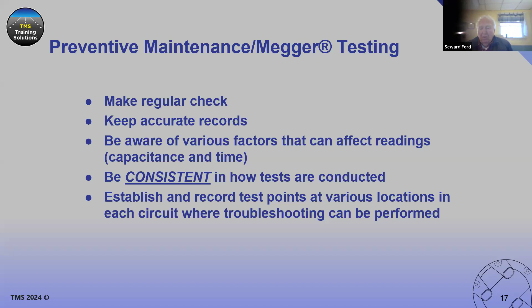So the time resistance method, I'm going to mention this just briefly. I haven't really had any comments from anybody on whether they ever use it or not, but it's an independent way of judging the insulation, fairly independent of outside factors such as temperature or circuit size. And it can give conclusive information without records of past tests. This is a quick man's test, I think you would say, if you don't have all the history, but by far you're better off having the history and looking at trending.